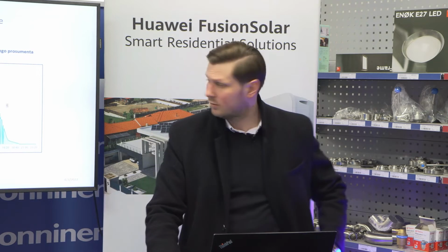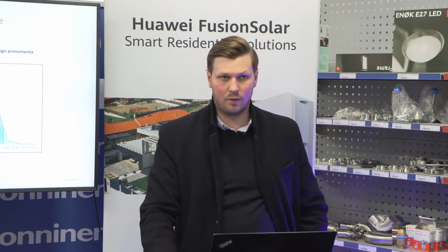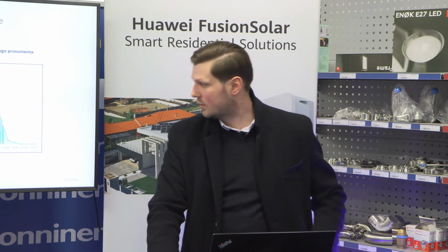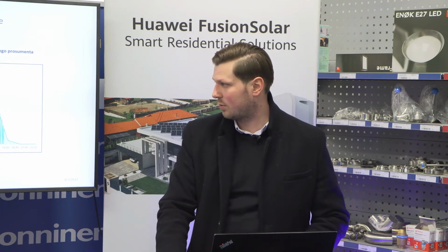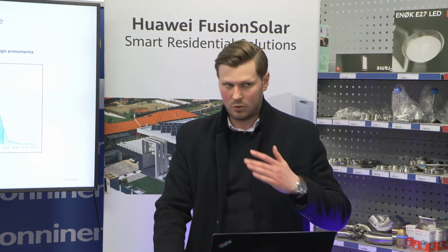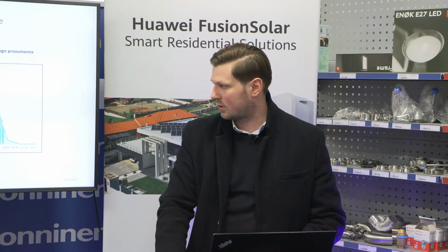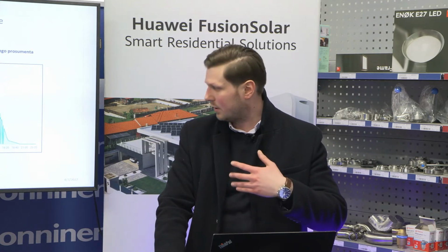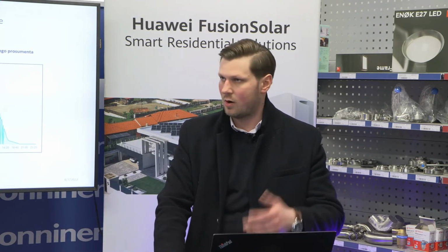So this is what the usual chart looks like when you have grid overvoltage all the time. If a customer comes to us with such problems, you should already have in mind that we have drops in production, meaning the voltage is causing the inverter to disconnect from the grid over and over again.